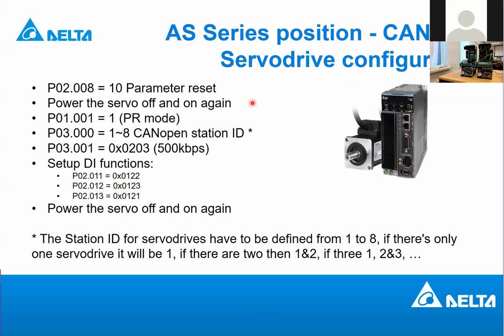if you look at this video, okay, I remove the USB because my USB is supplying 5 volts. So you can see now the drive is off. Then I plug my USB again. Let me power on the drive. Perfect. So you can see that I've successfully reset the drive to factory default. And you can see that alarm 13 is triggered, alarm 013.